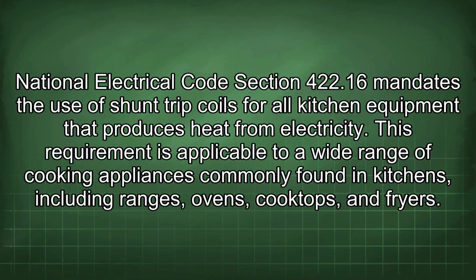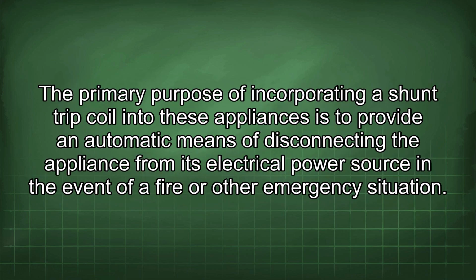National Electrical Code Section 422.16 mandates the use of shunt trip coils for all kitchen equipment that produces heat from electricity. This requirement is applicable to a wide range of cooking appliances commonly found in kitchens, including ranges, ovens, cooktops, and fryers. The primary purpose of incorporating a shunt trip coil into these appliances is to provide an automatic means of disconnecting the appliance from its electrical power source in the event of a fire or other emergency situation.